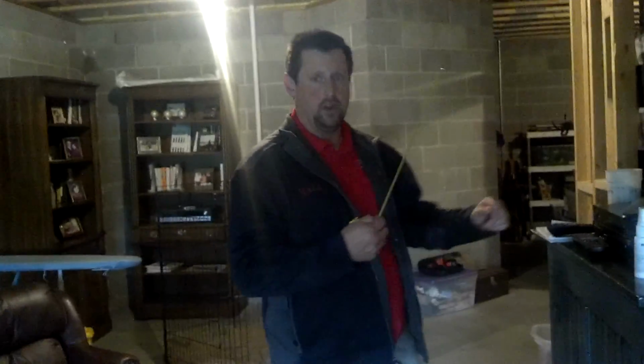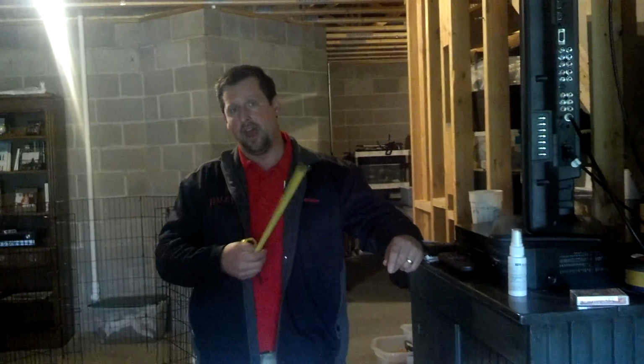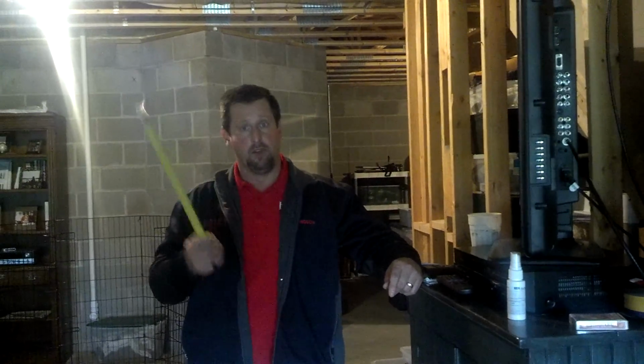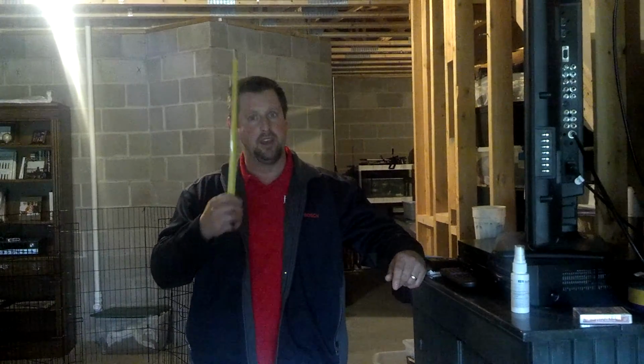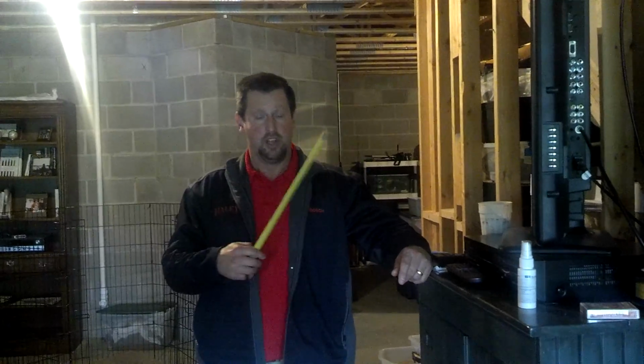Sure. And had I not seen the 2-zone over here, and you did not have the opportunity to put the 2-zone automatic in it, then we would have a different conversation. Because then you have one thermostat on the upper level, and that would be a reading for the whole house. When you run the fireplace upstairs, it fools that thermostat into saying we're all happy, and the basement gets very cold. But if you take advantage of that 2-zone automatic potential, and you have a thermostat up and a thermostat down, then it doesn't matter.